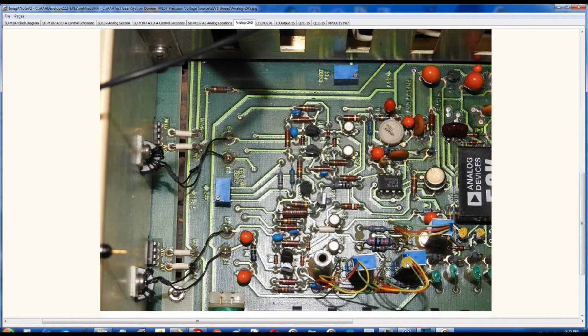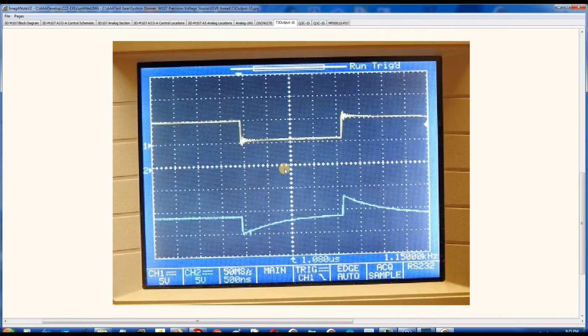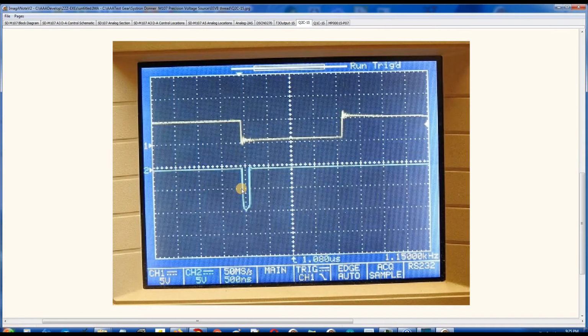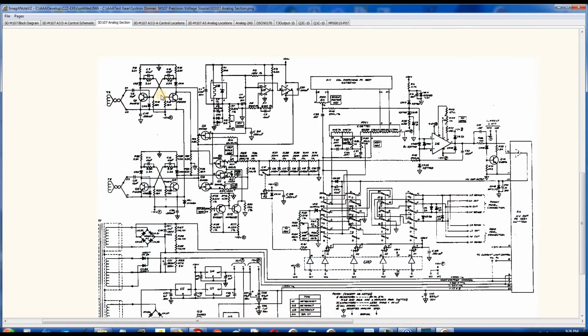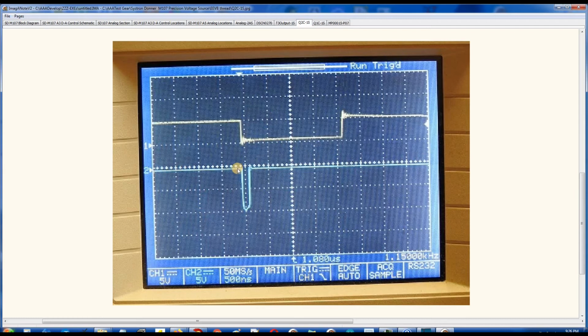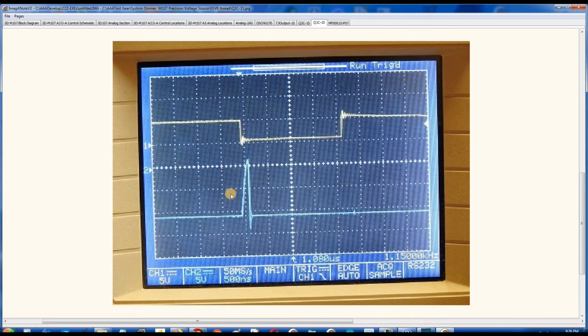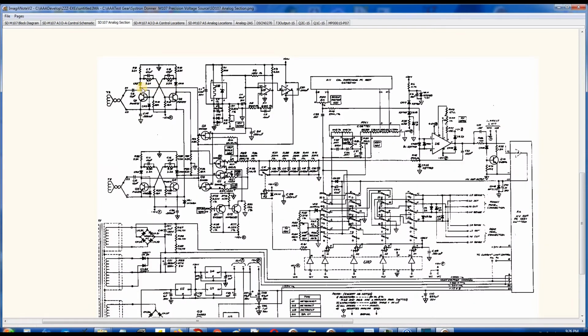These are also adjustments, these tall things with the wires hanging off, but the screws for them are on the bottom of the PCB. Oh, this is what I was talking about. There's the pulse width modulation signal going into the transformers, and this is what you see on the other side. A kick when it goes one way, and when it switches the other way, you get a kick in the opposite direction. Now, when it wasn't working before, this is the output of the flip-flops, these two flip-flops that are fed from the pulse transformers. This is what the output on one of them was. Instead of going low and staying low until the kick, it went high again. And likewise on the other side of the flip-flop, the other collector. That's looking at the collectors of these two transistors.